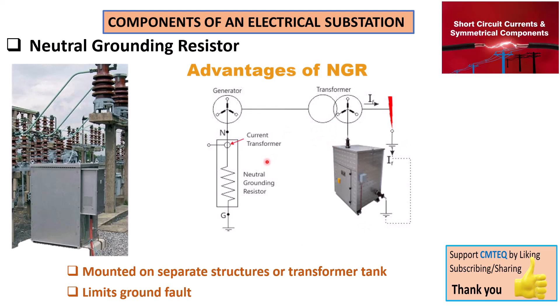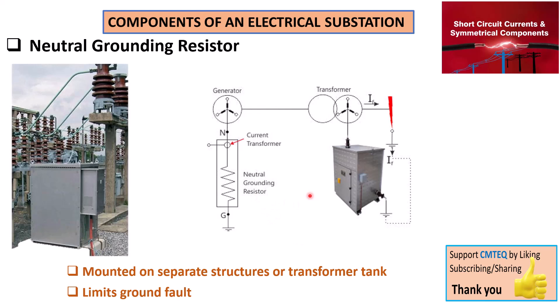Before we end this tutorial, let's look at some of the advantages of having this system in place. The chief advantage is to limit the ground fault, but you must ensure that coordination with the current transformer is not undermined. Having a neutral grounding resistor also enhances transient stability — when a fault occurs, the system can continue to operate until technicians are able to attend to the problem, providing operational continuity so things don't break down before someone can fix them.